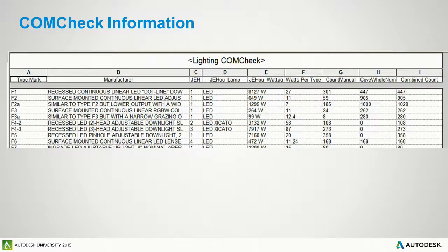It could be done where we could stagger the fixtures or we could do something, but we know that I have to round up. I can't just disregard that 2 inches that doesn't fall in my even dimensions. And so for a conservative approach for our energy code, we're going to tell it to round up, meaning we're going to need 1 more fixture to cover that.